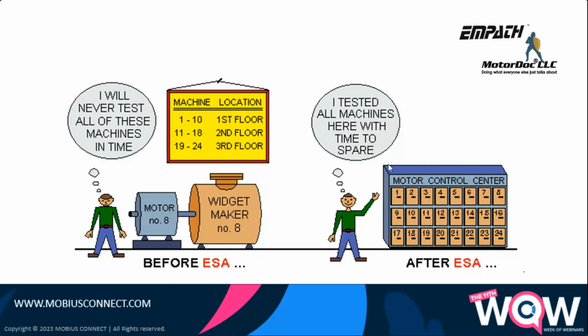Welcome to the world of IoT devices, right? Where we stopped doing one of the most important parts, which is the visual inspection. So if I take a look at a system, in this case, say a 300 horsepower motor, and this is with electrical signature analysis, here's my basic data. I've got input power of 193.5 kilowatts, output of 180 kilowatts. Everything in between are losses. That means at 81% load, the motor's operating at 95% efficiency. Pretty straightforward. Input, output, efficiency in between.